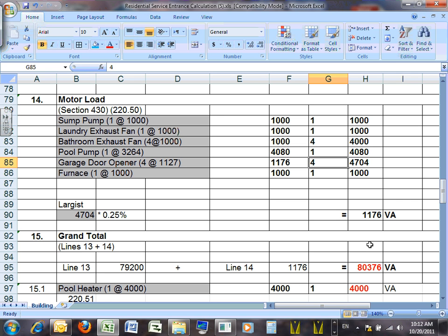The only place where you need to use the nameplate as the full load current is specified explicitly. How do you size cables? This 430.248 says full load current, and the nameplate says full load current. If it wanted to say the nameplate, it would say nameplate full load current. Look at 430.32 for the overload.